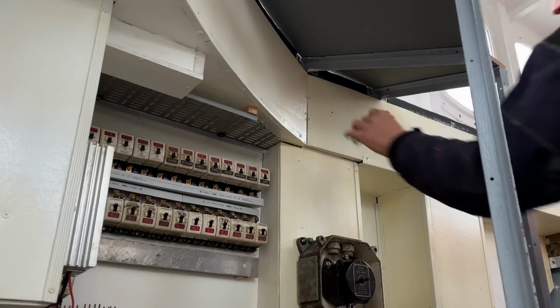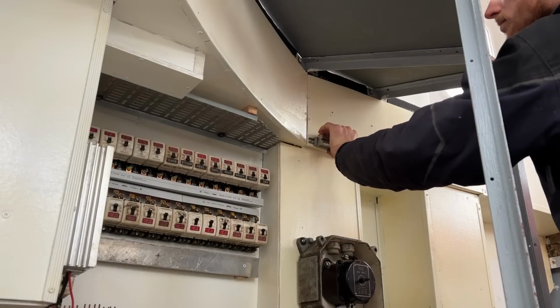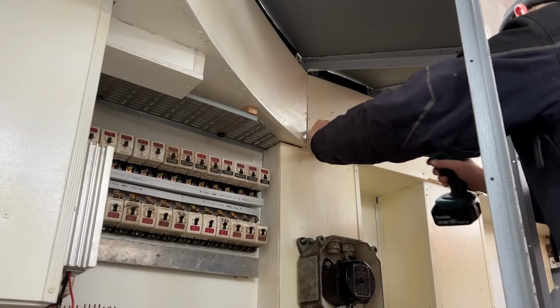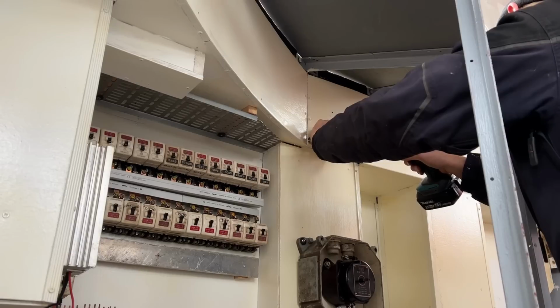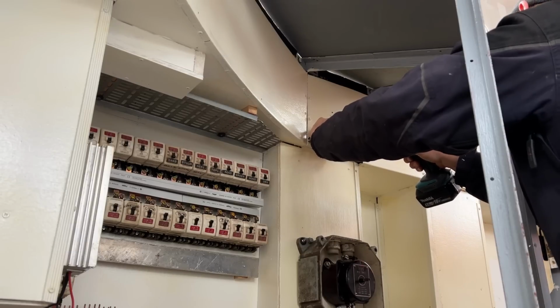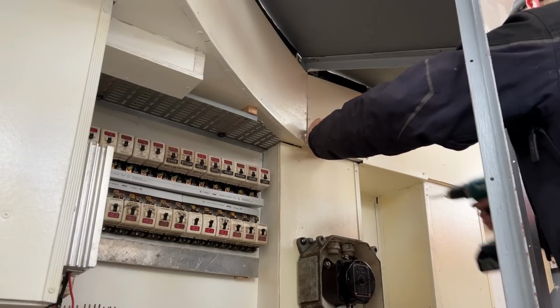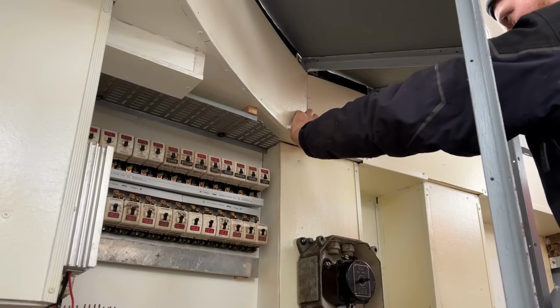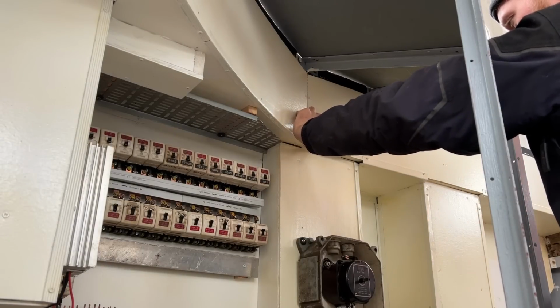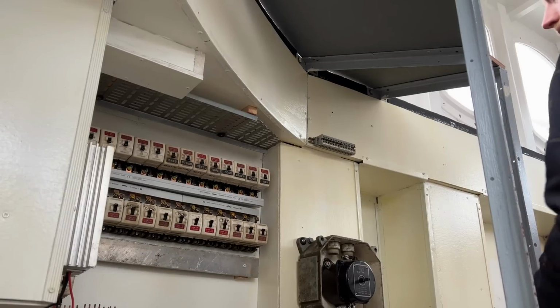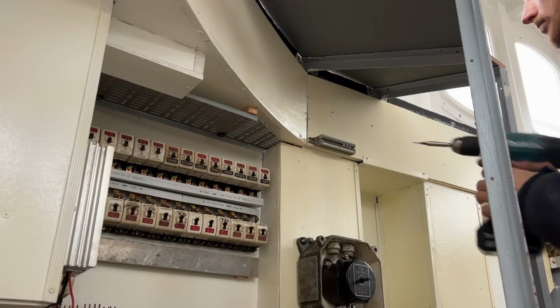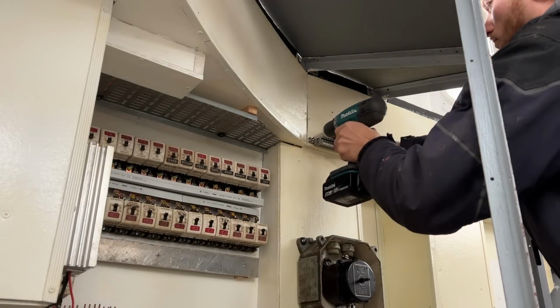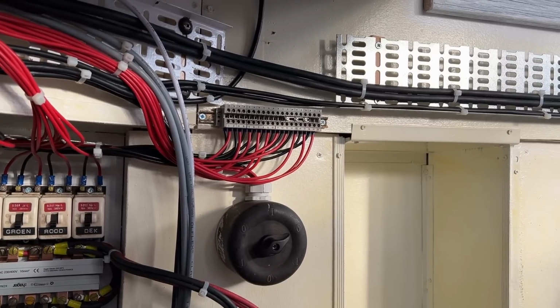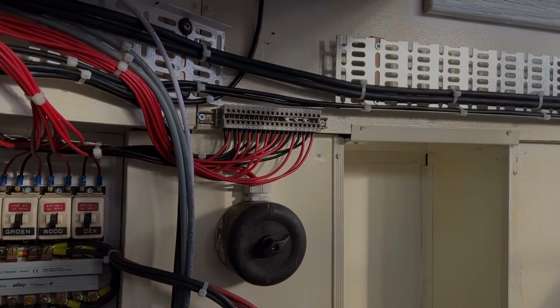It does take up much more space, so for the navigational lights I have to make an exception. Because the switches for the lights are on the front panel of the console and they only switch the positive line of the 24 volts. Instead of running a bunch of big 2-core cables through the whole console, I will install a terminal block close to where the cables exit the console and connect the negative wires straight from the breakers to the terminal block. The positive wires are also connected to the terminal block, but via the light switches.